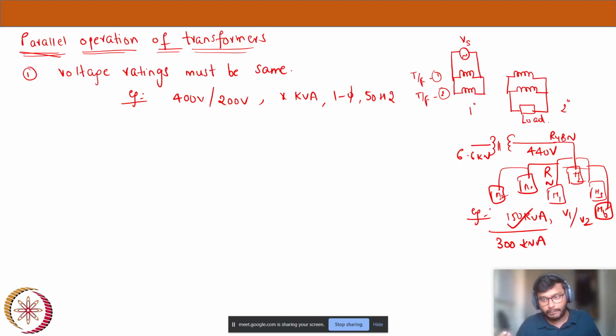And yeah, obviously when I buy a 150 kVA transformer instead of a 300 kVA transformer, I have saved half of the money, and in turn I am already using my existing healthy transformer of 150 kVA. Yeah. Now there are even more advantages of parallel connection of transformers.